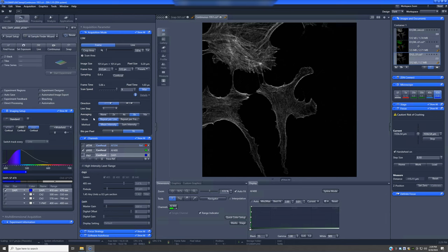Obviously, you pay a time penalty. So this is maybe if you don't have bleaching, not the first choice for where to improve quality. But if you do have bleaching, or if you run out of room with the laser, averaging is an excellent choice to improve the image quality.